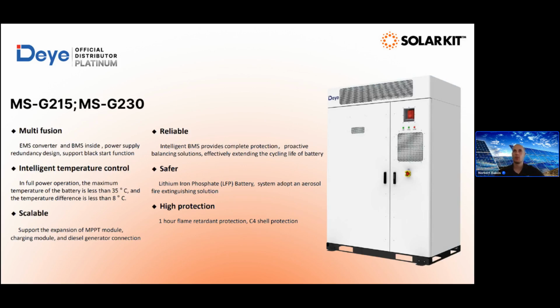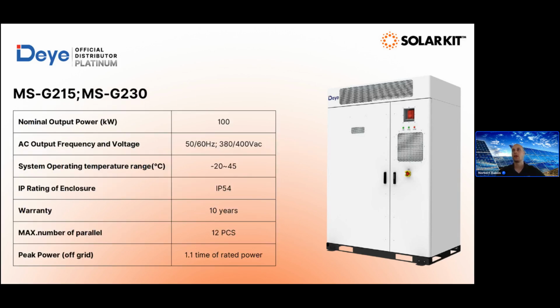And if we jump one scale higher for the AC coupled, because these were both DC coupled batteries, because you had the inverter on the side, this one is an AC coupled 215 and 230 kilowatt hour battery. You have the 100 kilowatt PCS inside. It's also IP54.